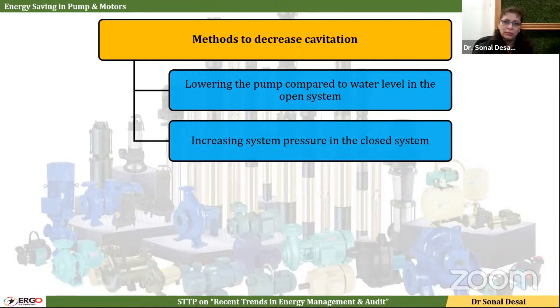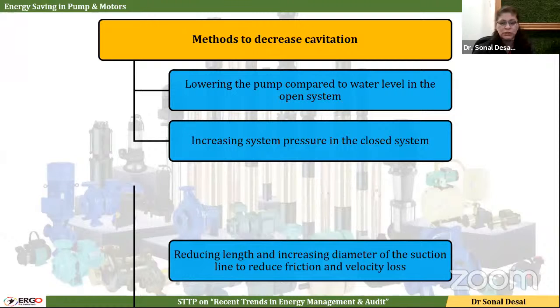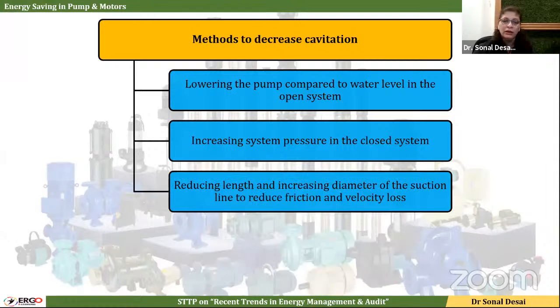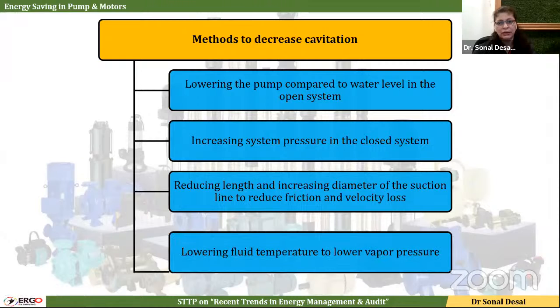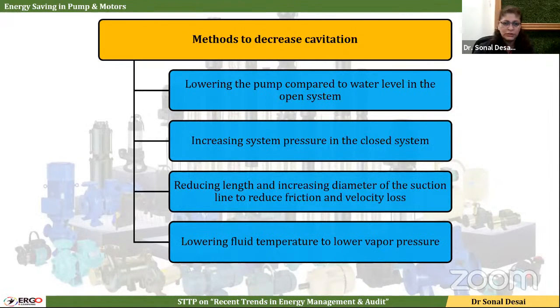Here are some more methods to decrease cavitation. We can lower the pump placement so that the pressure will be changed and cavitation will not occur. We can increase system pressure in case of a closed system. We can reduce the length and increase the diameter of the suction line. As length is decreased and diameter is increased, again it will affect the pressure and the suction pressure will be lifted.